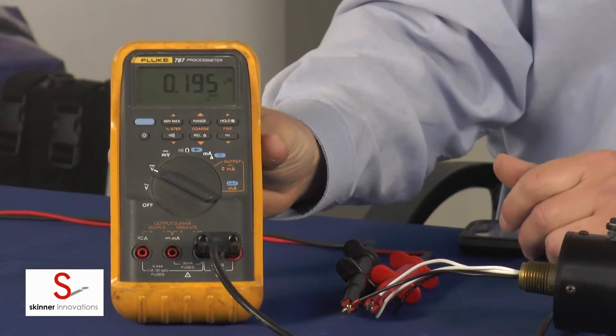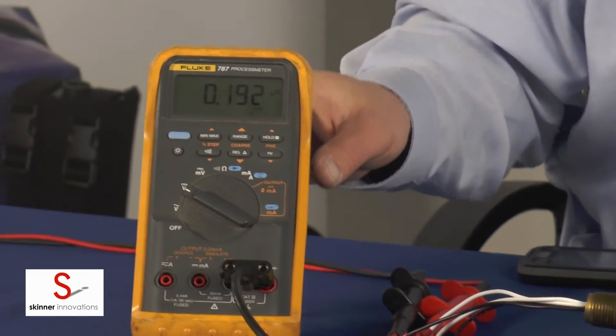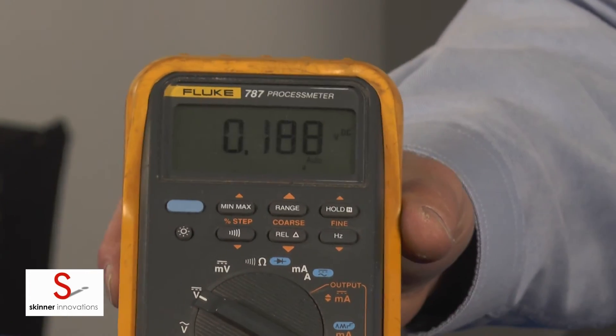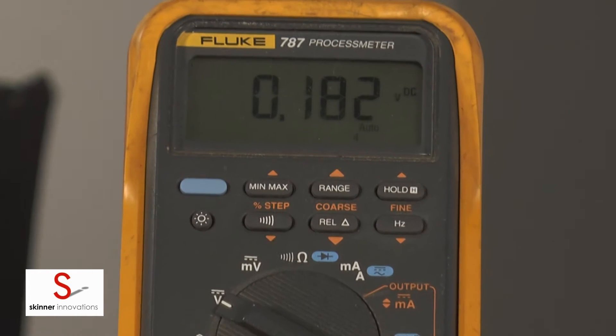Okay, it's been five minutes now. The HST has held the temperature for five minutes. The temperature has now turned off and the detector has reset. It will stay off for 45 seconds as the temperature drops and then it will turn back on.